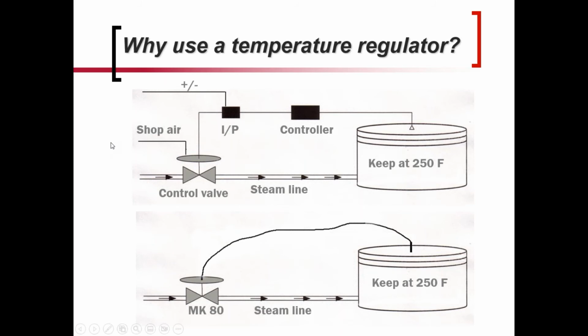And this works well, but the main difference that you can see and figure out is the amount of cost that's involved. So if you have a fairly benign application, we're just keeping that tank at 250, and you can do it mechanically. Think of all the elements that you've now removed from the equation. You don't have to wire it to a controller, to a PLC or a DCS. You don't have to run shop air to it. You don't have to have an I to P that converts a 4 to 20 signal in order to make that happen. So that's one of the biggest advantages. It's just cost, and don't look at it just as material cost, because there's obviously labor costs involved with this when you're running conduit and wire and all that. So there's more to it than just the valve versus control valve and I to P and temperature sensors.